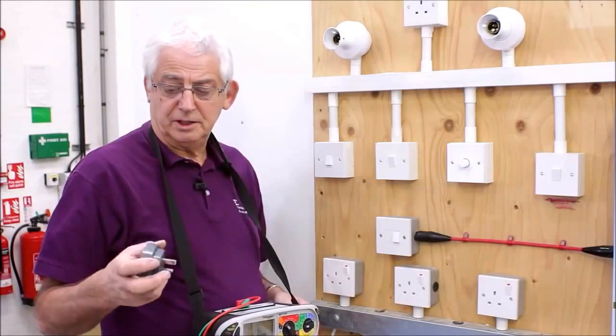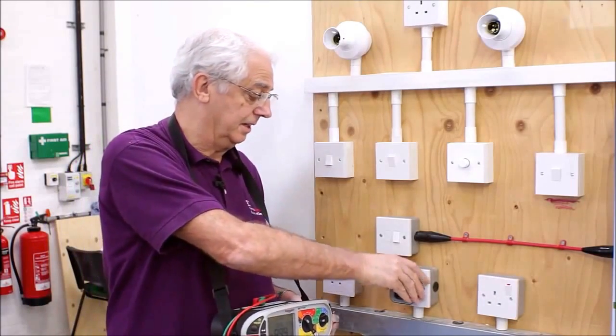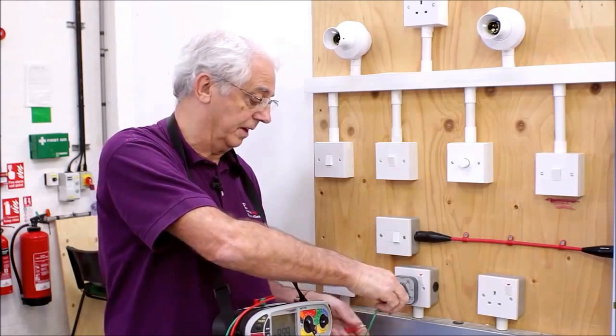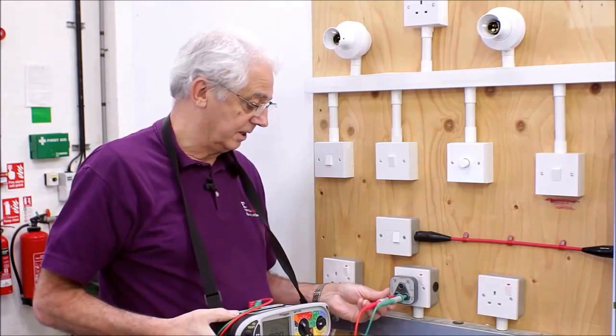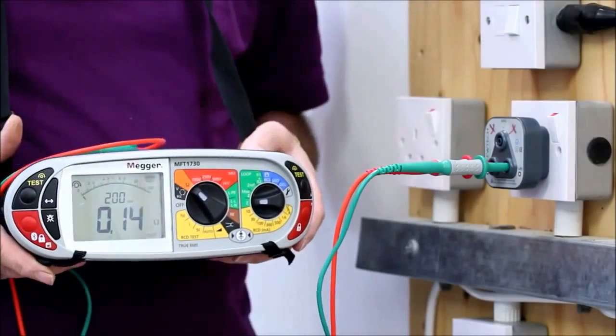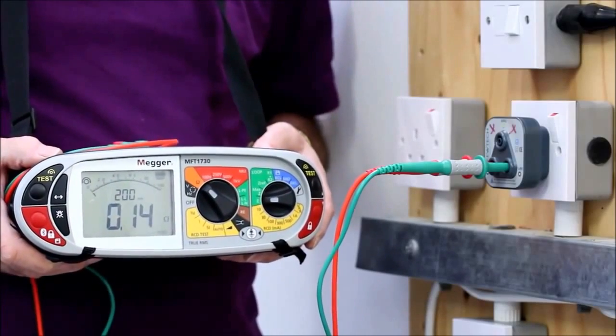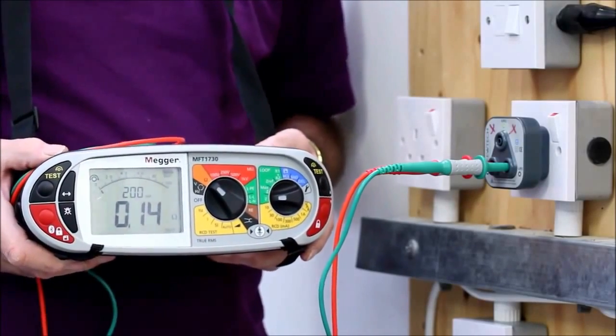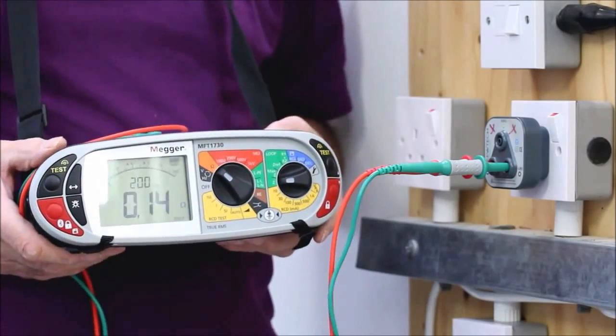I'm now at the last socket, just going to repeat the test again. Up till now, all of the values have been correct. If I take a reading again, the value should be around 0.15. And as I said, providing it's within 0.05 of the original value, we haven't got too much of a problem.